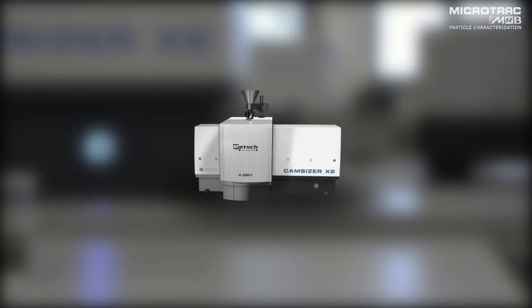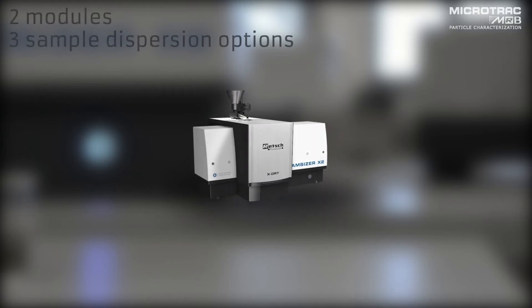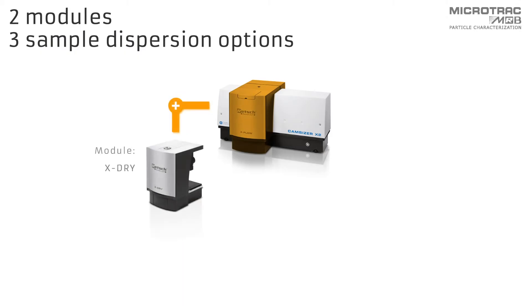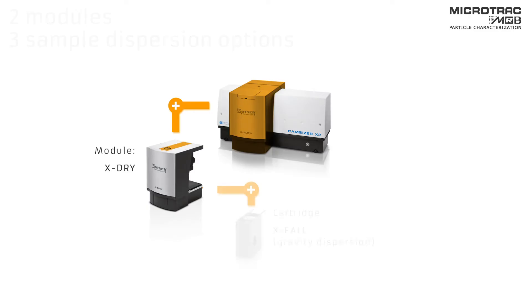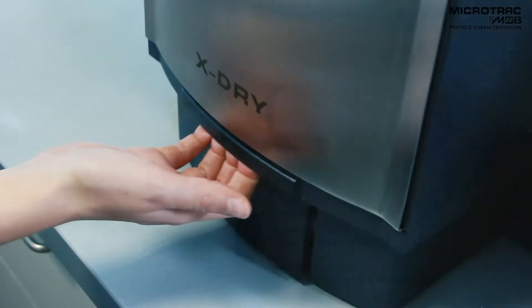The CamSizer X2 is suitable for measuring dry and wet samples, featuring two modules with three different sample dispersion options. The dry dispersion module X-dry can be equipped with two different cartridges. The gravity dispersion cartridge X-fall is used for pourable solids and free-flowing bulk materials.